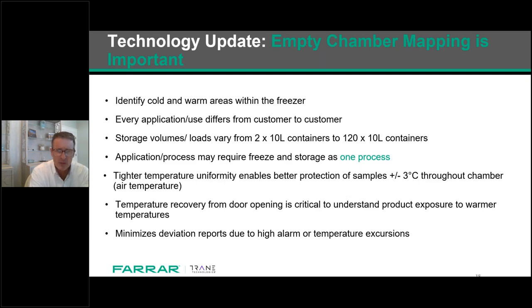And a lot of folks will say, well, we also do a PQ, which is a performance qualification. And this is where product is added or simulated load, and then temperature mapping is repeated. So again, keep in mind having more product or racks within the freezer will greatly improve its temperature uniformity and temperature recovery. But imagine a freezer with only one container or a few vials, how long it takes to recover to control set point of minus 80. So I will now turn it over to Steve. Next slide, please.